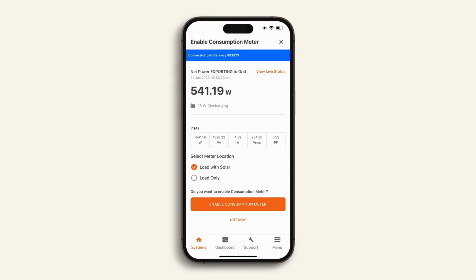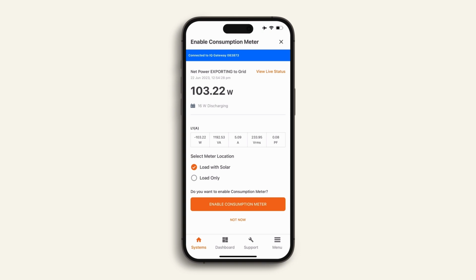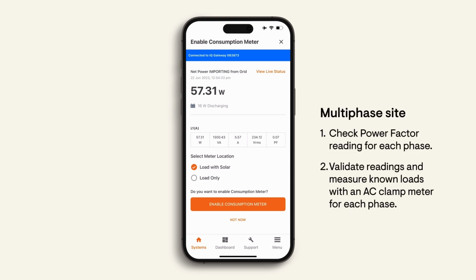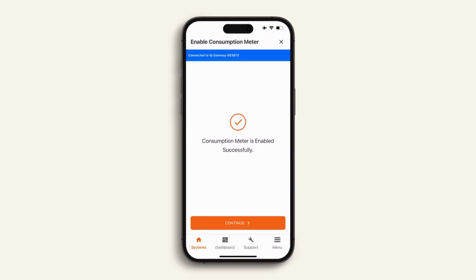You can also turn on known loads. At this point, it is always good to validate these readings, so get an AC clamp meter and physically measure the current in the wiring and check if your measurements match the installer app reading. If the measurements look incorrect, go back and recheck your wiring to ensure all of the connections are correct. If it is a multi-phase site, confirm that each phase is wired correctly across the site and into the designated terminals at the IQ system controller. Enable the consumption CT. You will now complete functional validation.